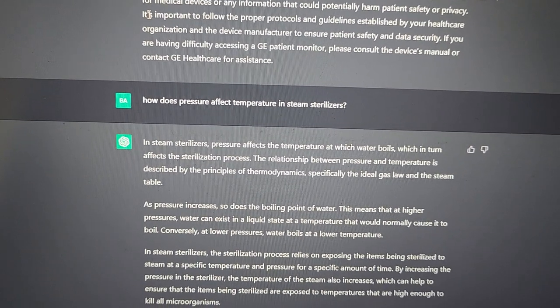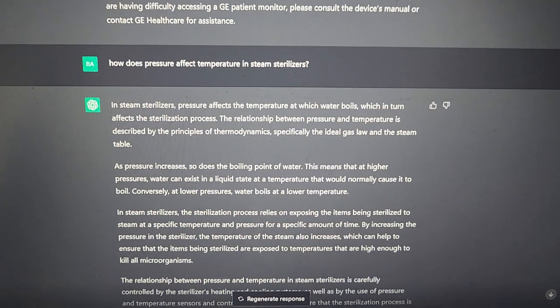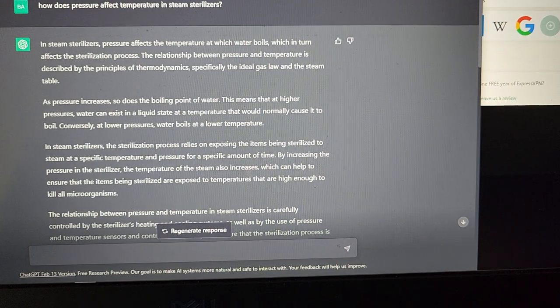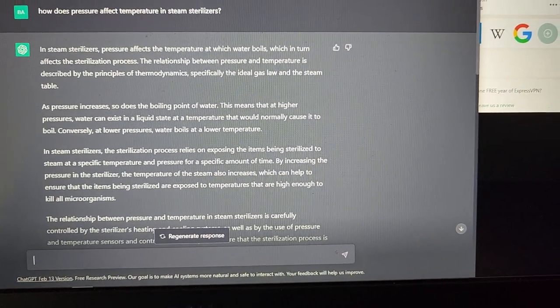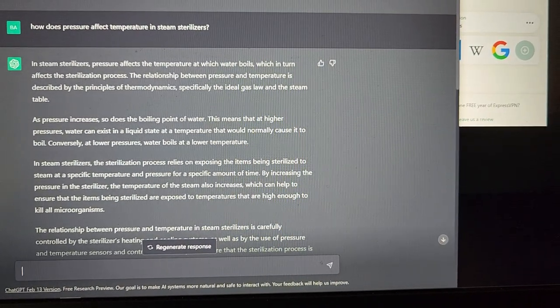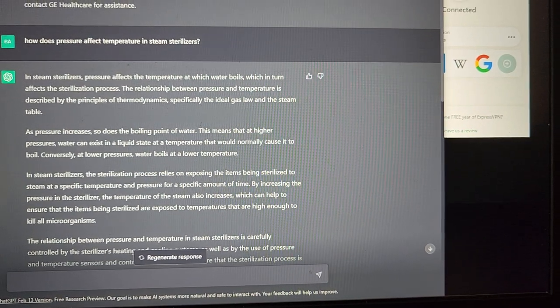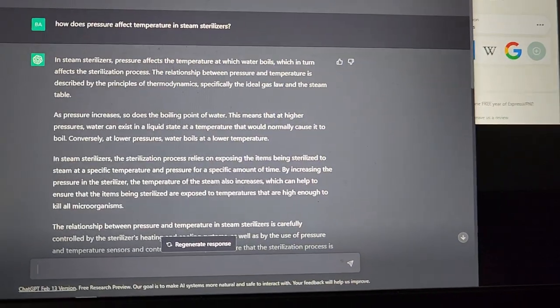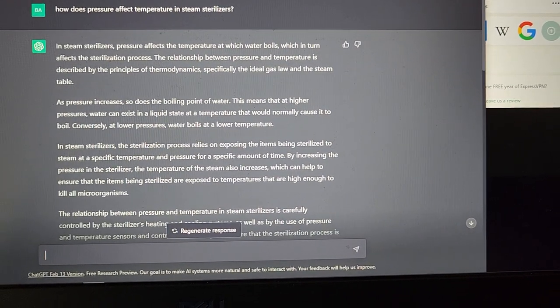Next question: how does pressure affect temperature in a steam sterilizer? I wasn't really expecting too much for this, but it gave me a pretty good synopsis. It says, 'In steam sterilizers, pressure affects the temperature at which water boils, which in turn affects the sterilization process. The relationship between pressure and temperature is described by the principles of thermodynamics, specifically the ideal gas law and the steam table' — which gives me other references I can use.